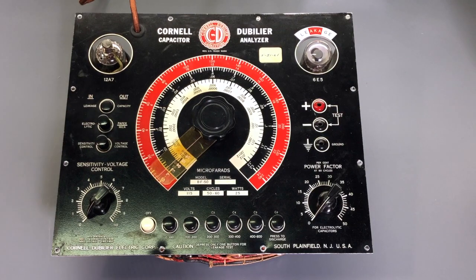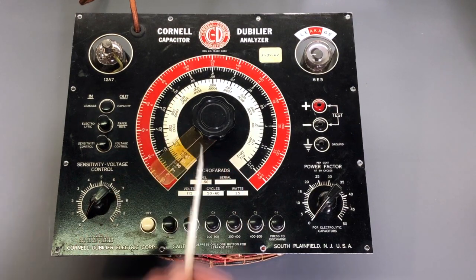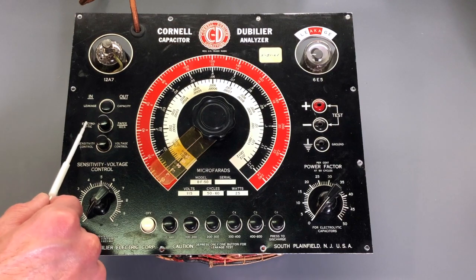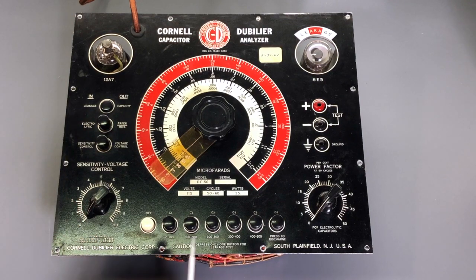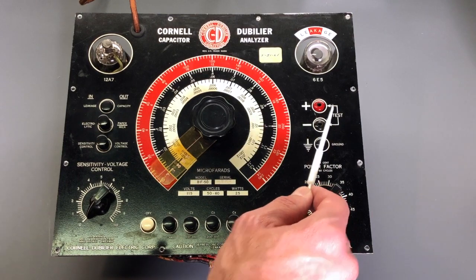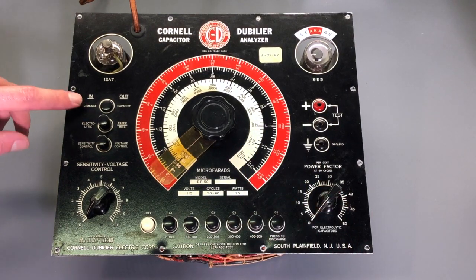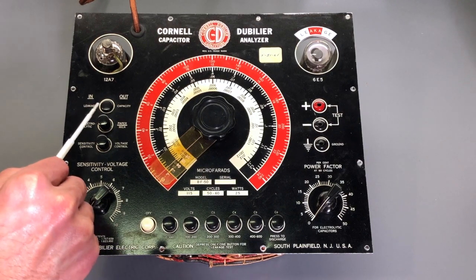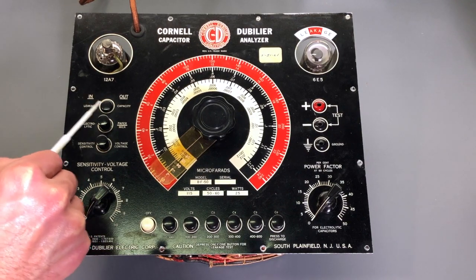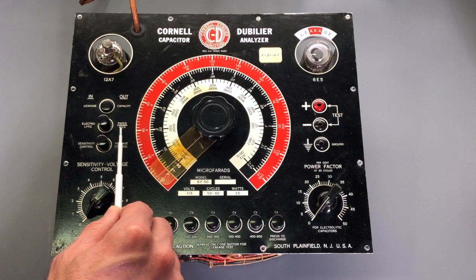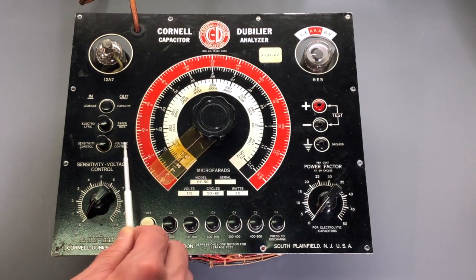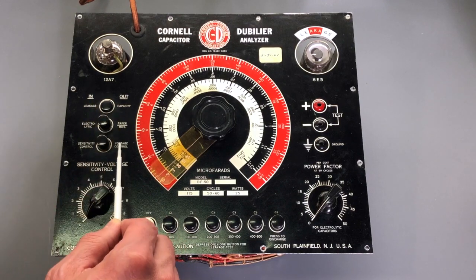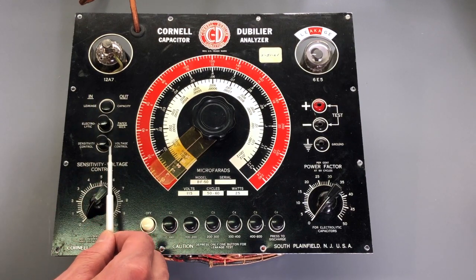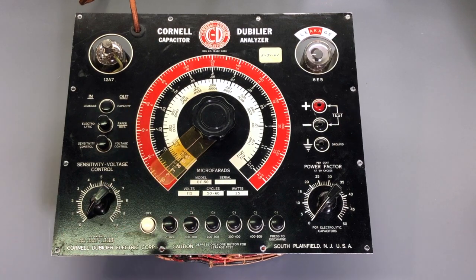in position. The switches down here control, of course, power and the various capacitance ranges when doing the capacity test, and the voltage ranges on the electrolytic leakage test, and those voltage ranges are the voltages applied to the capacitor under test. So starting over here, the top button is in the leakage position, which is in. We'll start with the paper and mica test, so that's out or up. And the voltage control is used in the leakage test. However, it's not used in the paper mica test, but we'll leave it in the up position or out position.